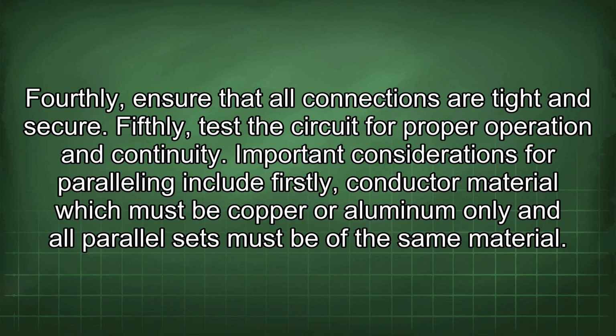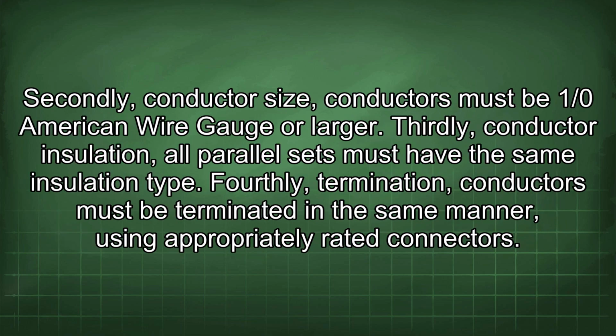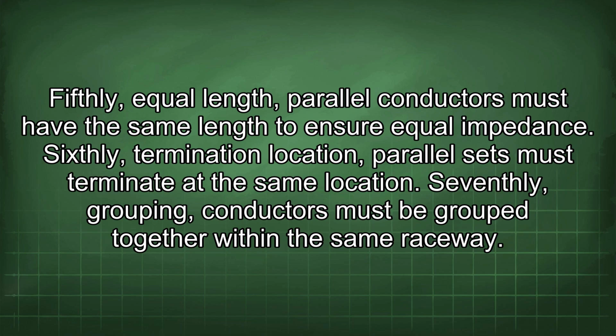Important considerations for paralleling include: firstly, conductor material, which must be copper or aluminum only, and all parallel sets must be of the same material. Secondly, conductor size. Conductors must be 1/0 American wire gauge or larger. Thirdly, conductor insulation. All parallel sets must have the same insulation type. Fourthly, termination. Conductors must be terminated in the same manner using appropriately rated connectors. Fifthly, equal length. Parallel conductors must have the same length to ensure equal impedance.